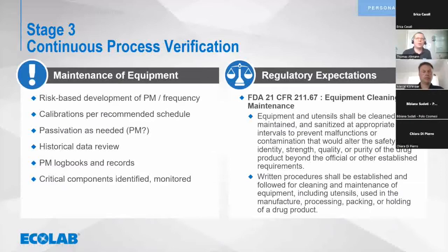So if your performance is at the same level as before the maintenance, and you would also take a risk-based approach to identify what has to be done at the maintenance level. If your temperature is very important, you might want to do maintenance on the temperature sensor more often than on the conductivity control of the rinse water, because that may be less sensitive for your process.